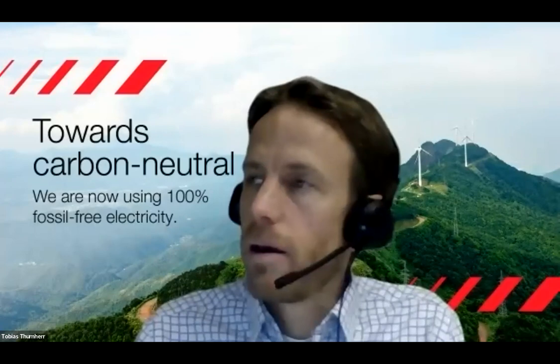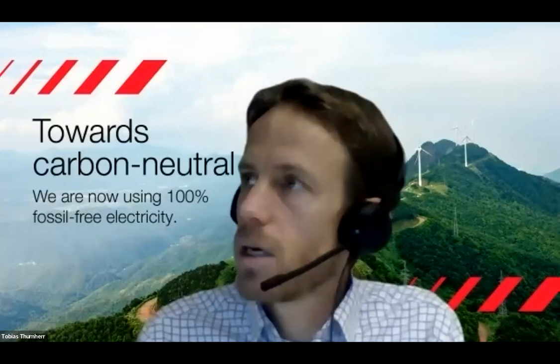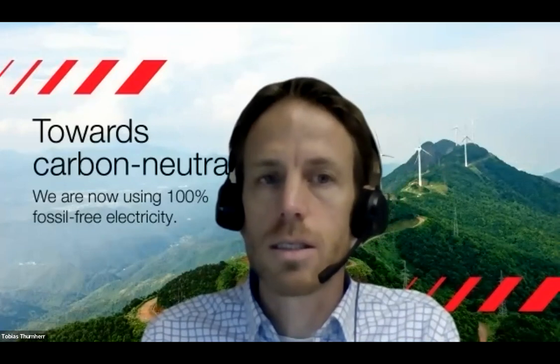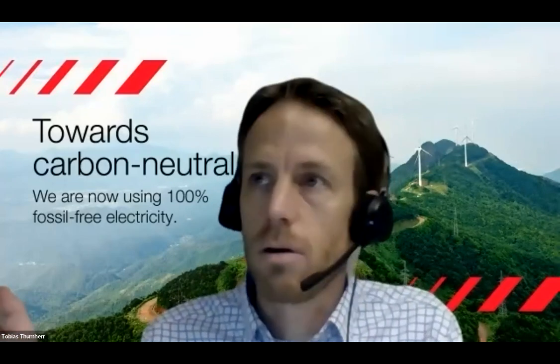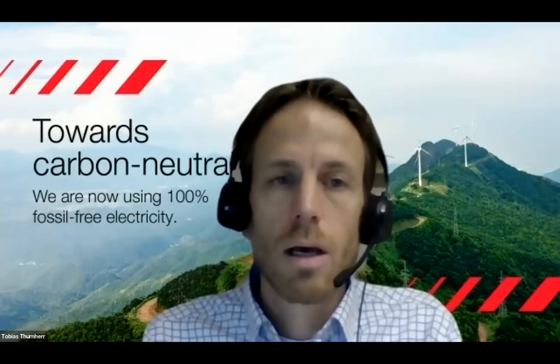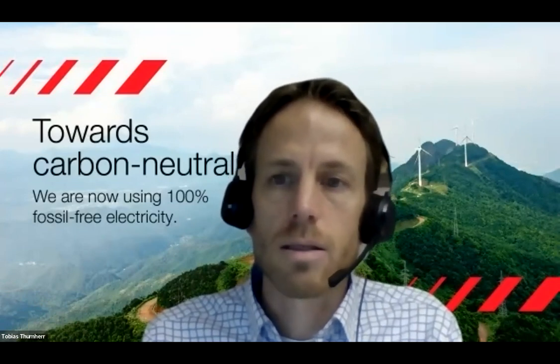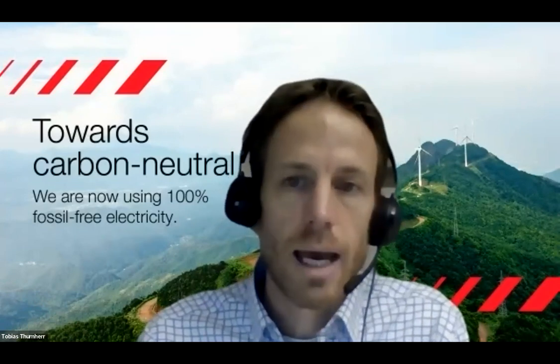Thank you. We're getting close to the end of the questions. Glenn, are SFCs adequately rated, tolerant to cope with numerous short circuits as typical on most railways with reduced overhead line clearances? Yes, the SFC is not being damaged each time it sees a short circuit, and then after 100 it just breaks down. So I think the answer to this question is yes. It can handle a large number of short circuits.